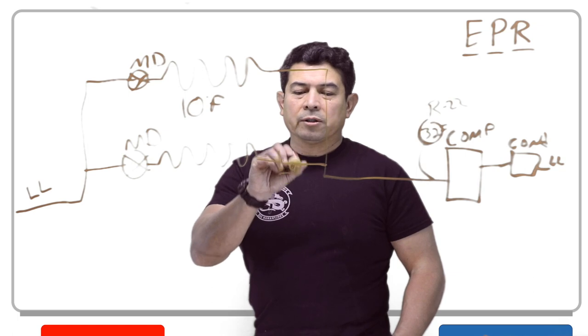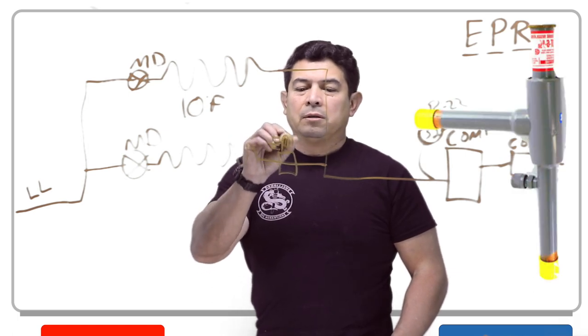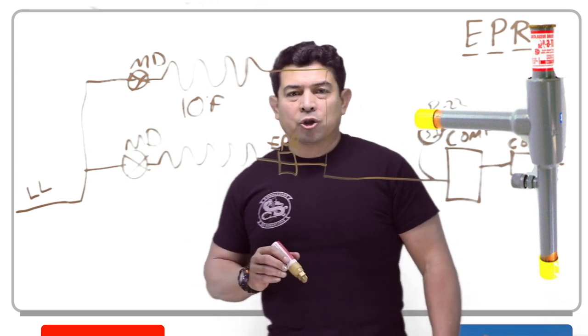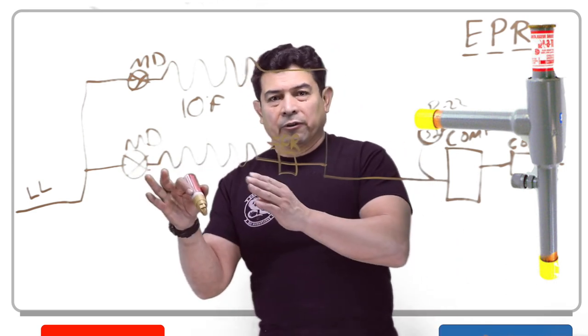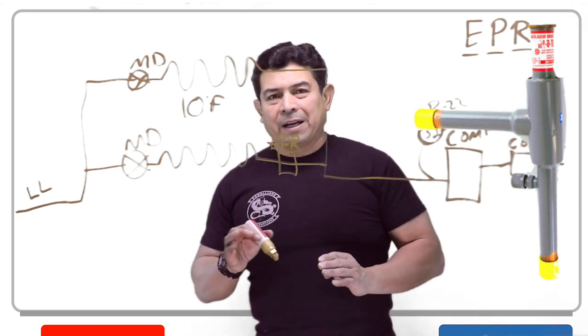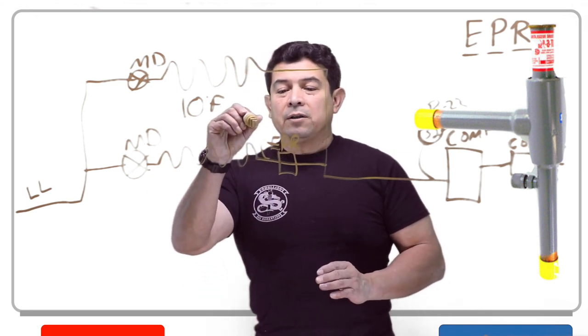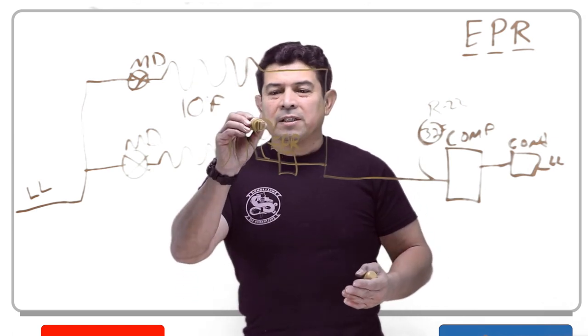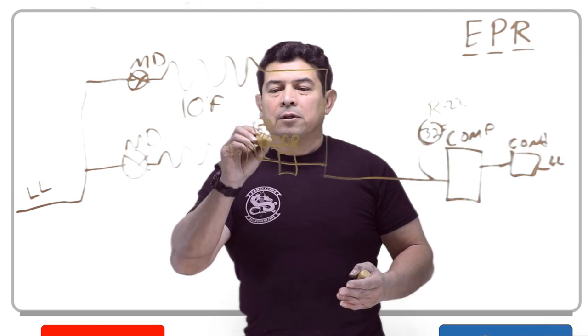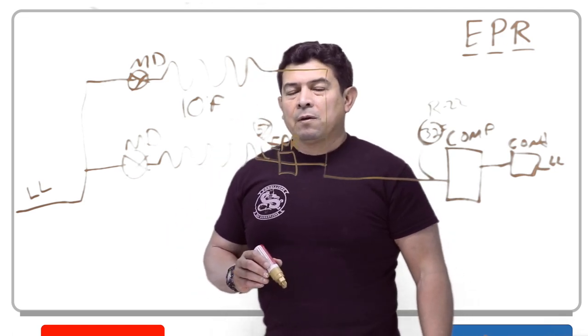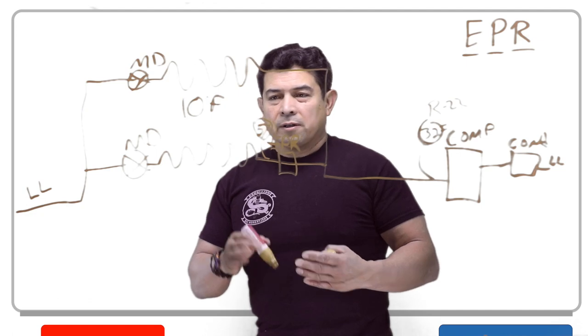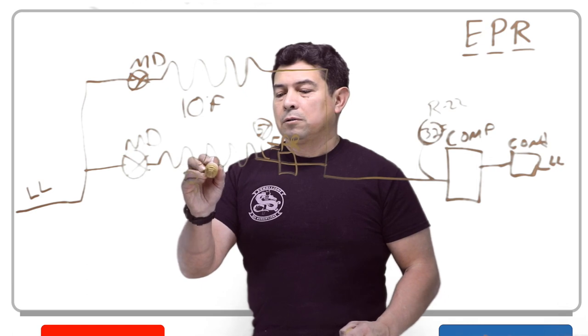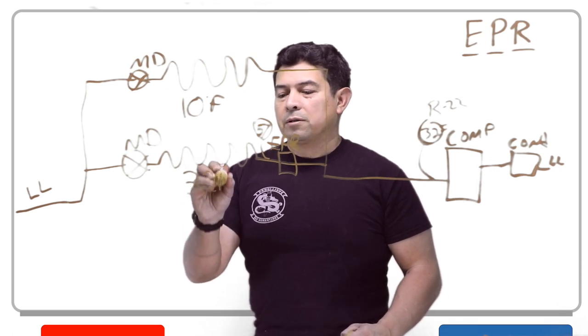So what we're going to do is put an EPR valve right here. This evaporator pressure regulating valve is going to back up the refrigerant, back up the pressure in here. We're going to maintain this pressure at 57 PSIG. When we look this up in the PT chart, 57 cross-references to 32 degrees Fahrenheit.